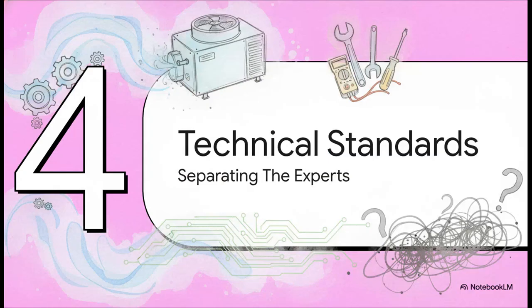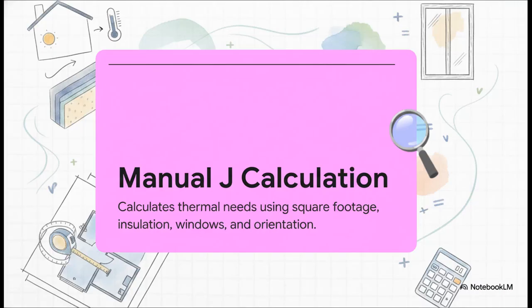All right, Chapter 4: Technical Standards That Matter. This is how we separate the real experts from the guesswork artists. It all starts with the math. Proper sizing for a new system isn't just looking at the old unit and matching its tonnage. Real experts use what's called an ACCA Manual J load calculation, a precise mathematical standard that determines a home's true thermal needs based on square footage, insulation levels, window area, internal heat gains, and even the direction your house faces. It's absolutely required to prevent the short cycling and high humidity issues we just talked about.